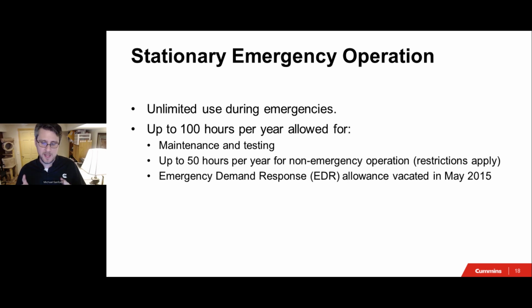I saw a question come through in the pre-registration that asked about demand response for emergency engines. It's no longer allowable. That position by the EPA was vacated in 2015. We're 8 years past that at this point, and I'm still hearing questions about it. The DER or EDR provision in the EPA within Title 40, Part 60 was vacated 8 years ago now. Not allowable. And I'll talk about what products you have to use in order to operate in that space.